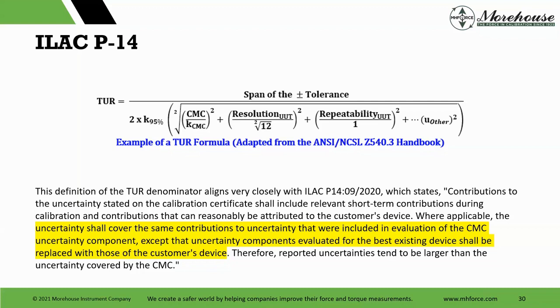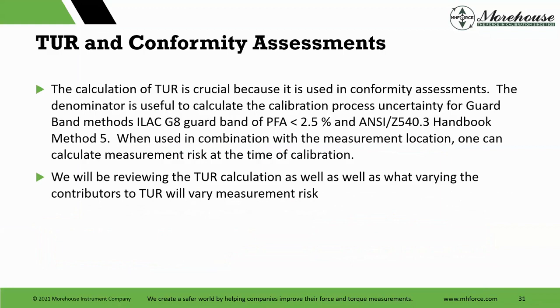And it says short-term contributors during calibration, so those short-term ones are resolution, repeatability, and then we added other error sources to capture the environment and just a catch-all. And we have that in the download on the PFA. So we need to grab that. If we're going to do that calculation, we're going to calculate our calibration process uncertainty, which is our measurement uncertainty, really at the time of calibration. It includes all the contributions from the unit under test, that's a good formula to use.